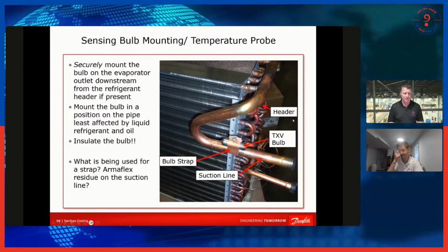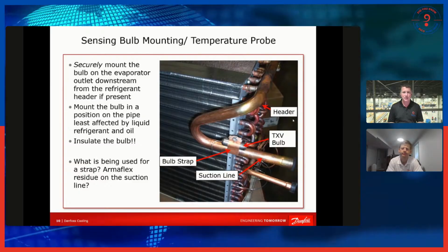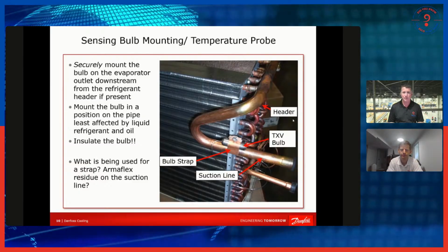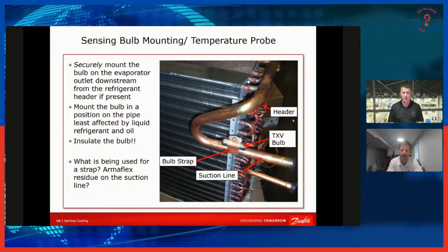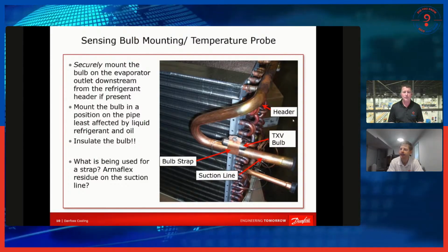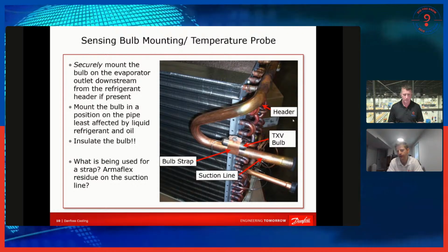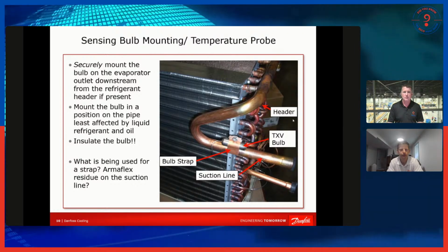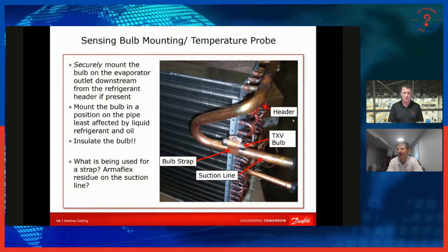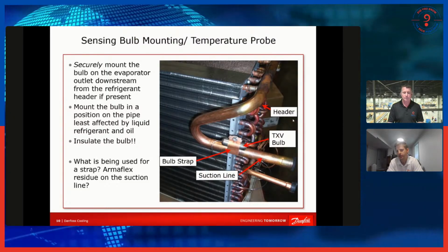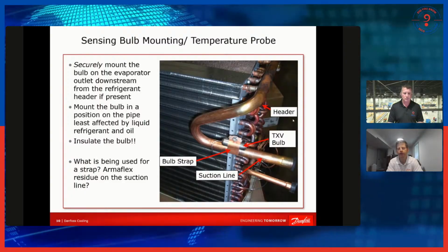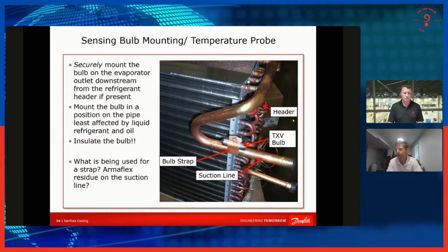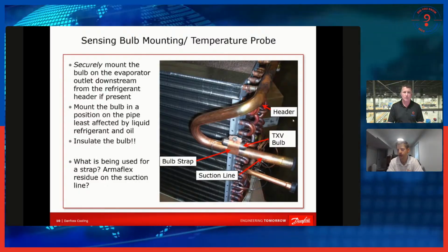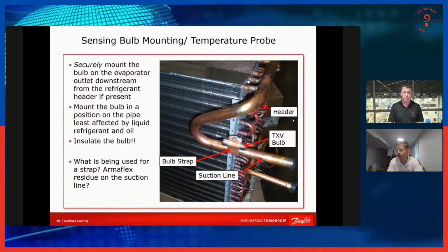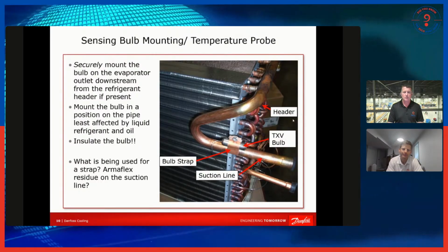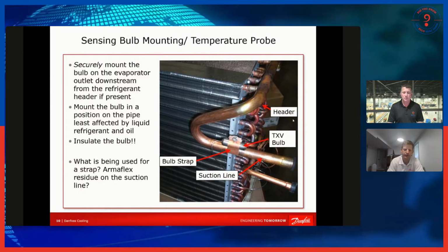What about insulation differences? Do we see much difference between the amount of insulation required for a thermostatic expansion valve and the temperature thermistor for an electronic expansion valve? I've not seen any big difference in the requirement there. You can get away with not using it and it'll still work, but it's better to have it. And I don't really think I've seen a big difference between the two in terms of whether you need or don't need insulation and whatnot. I do think some of it does depend on if you're in the airstream or not. If your suction line is outside of the airstream, then not having insulation becomes less of a problem.